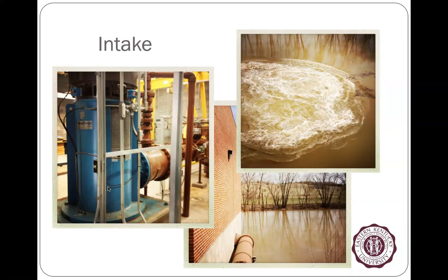So intake. So at the Richmond water plant, on the Kentucky River, even on a muddy day, they draw water. Even on the muddy days, it actually cleans up better because it kind of settles like a big blanket in their water plant. The screens can periodically get clogged. They have a big air compressor that they can shut the water off, reverse this, and throw a big blast of air, and it looks like a depth charge going off in the river. So they can clean the things off when they need to.